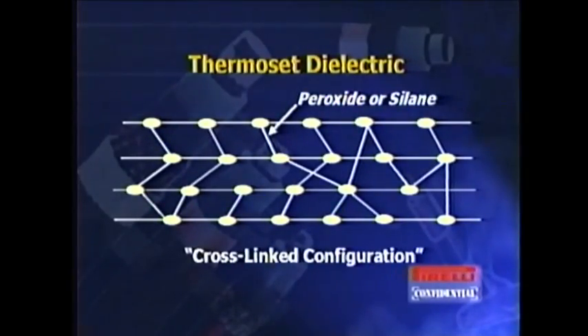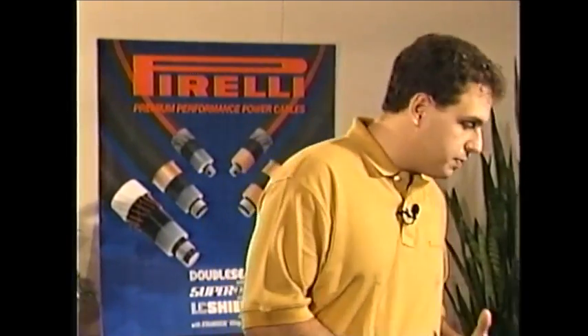So in order to prevent this from happening, what we use is what's called thermoset materials. Those thermoset materials, also called cross-linked materials or vulcanized materials, those terms are interchangeable. The properties of those are that you can heat those to high temperatures and they won't melt. They can have some deformation, but the point is they won't melt off of the cable. So this makes it ideal for applications where you have high heat, such as a power cable where you're drawing current which will generate high heat.